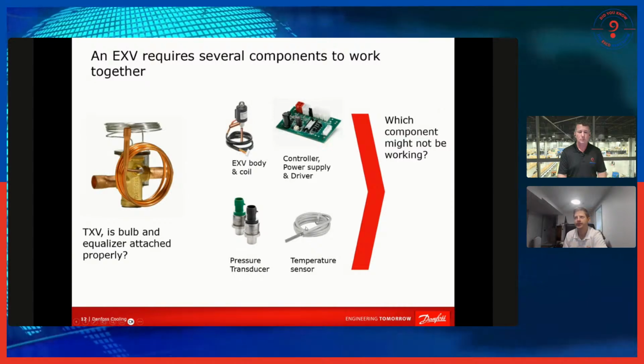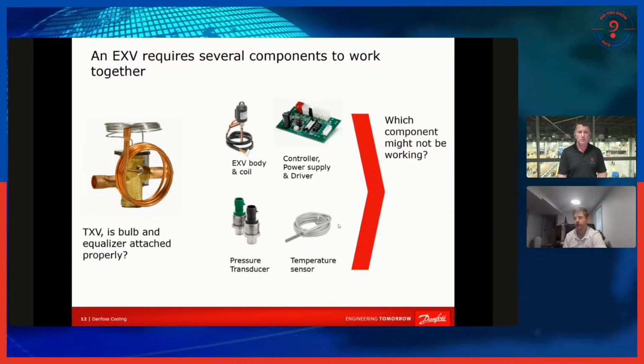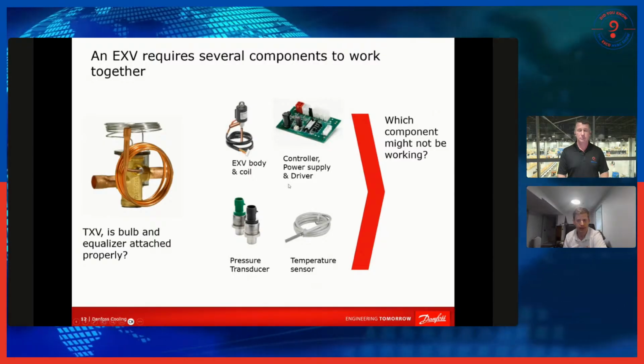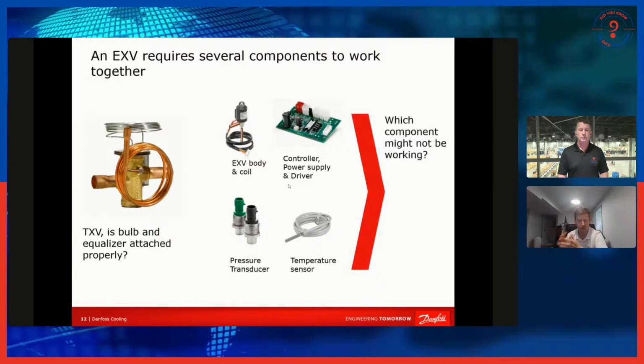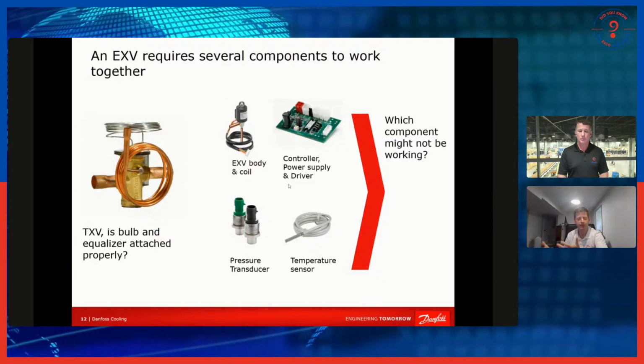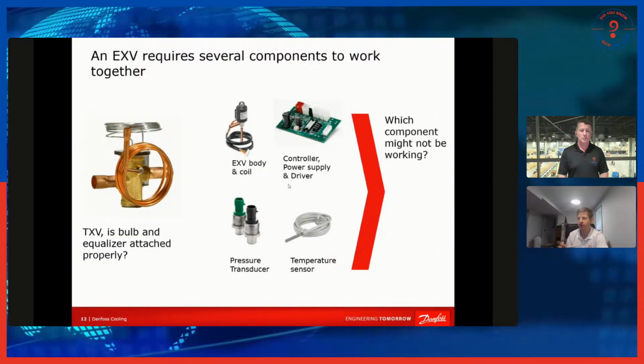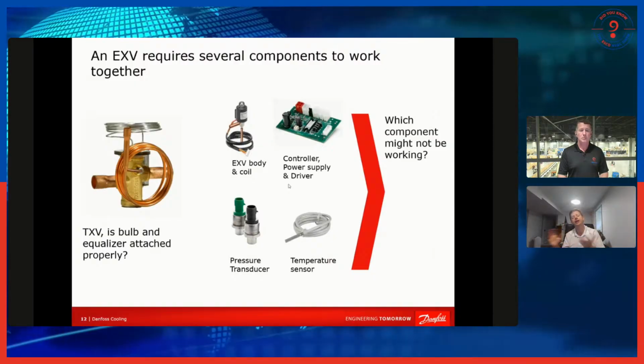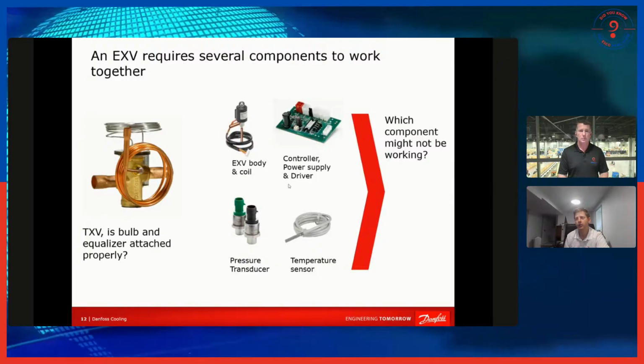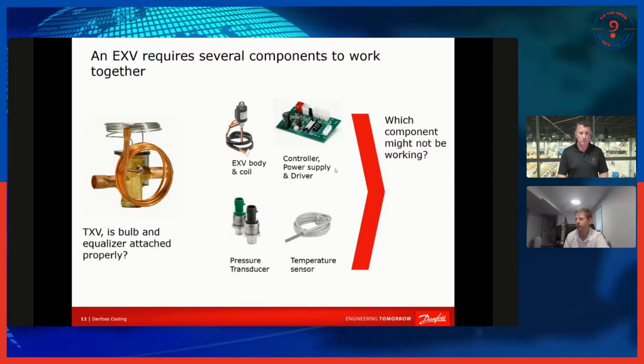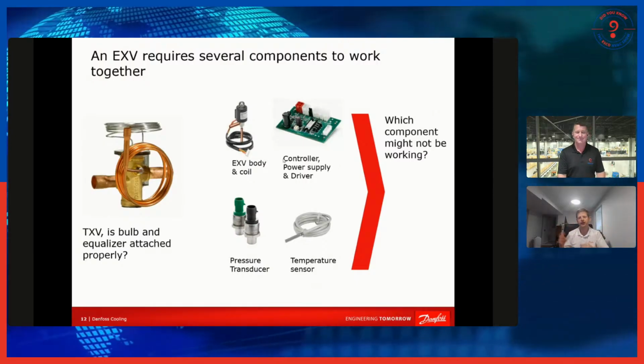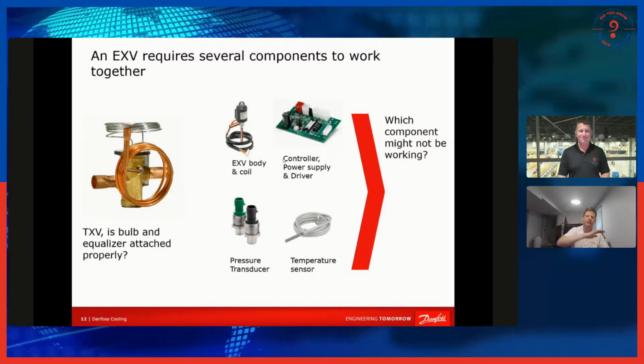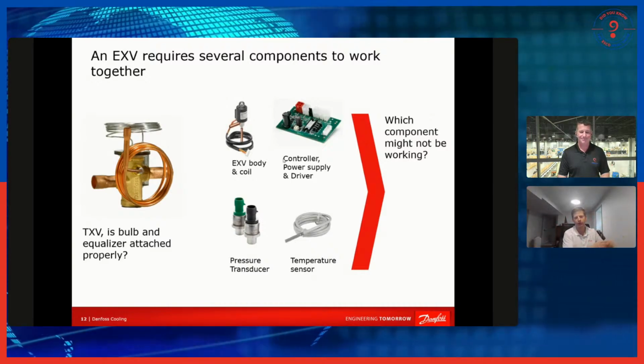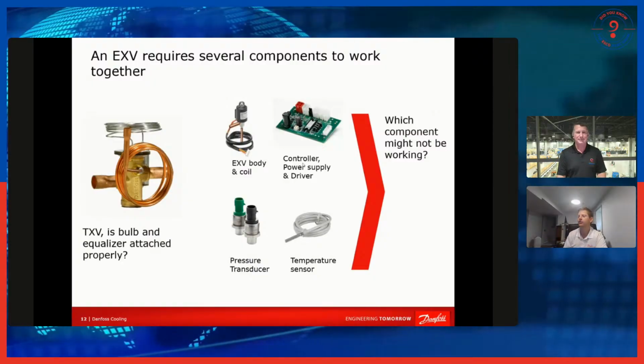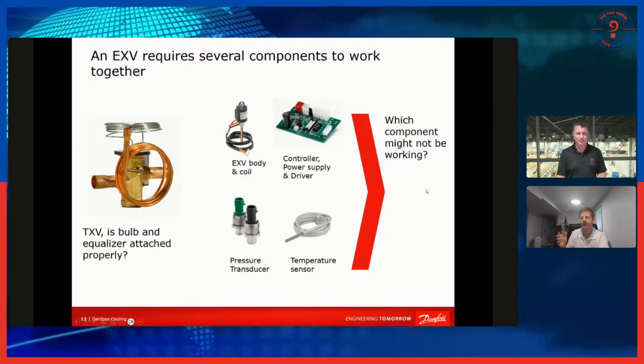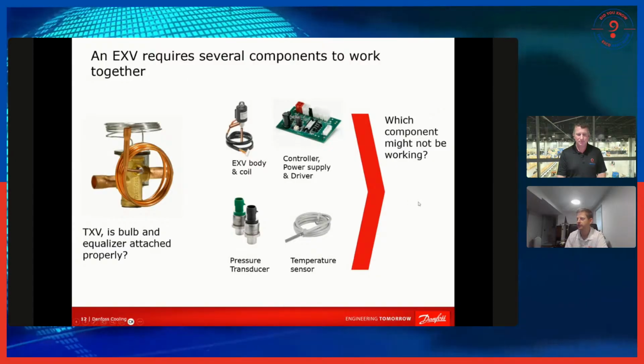A temperature probe. And a lot of the advice for how to troubleshoot through this, you kind of need to know what controller is being used by the manufacturer. And you have to kind of troubleshoot that based on the manufacturer's recommendations, based on what it's able to communicate out. But I've got some good general advice for things that you can do when you encounter one to try and troubleshoot your way through it. And it's kind of all, to me, always based around how do I start narrowing things down? How do I start chopping? Okay, I know this is working, so now I can turn my focus to this. And it's how do I rule certain things out? Process of elimination troubleshooting is generally how I think through things.